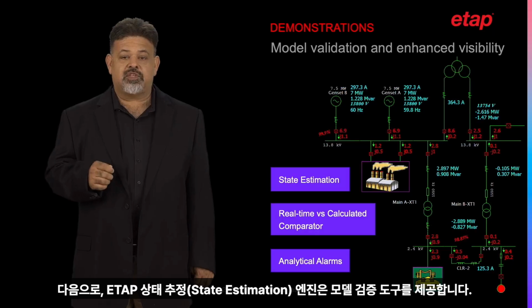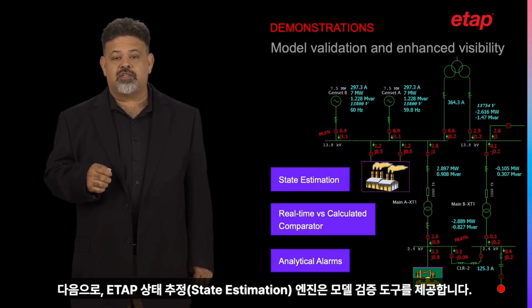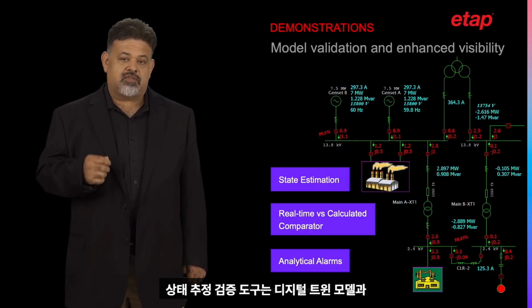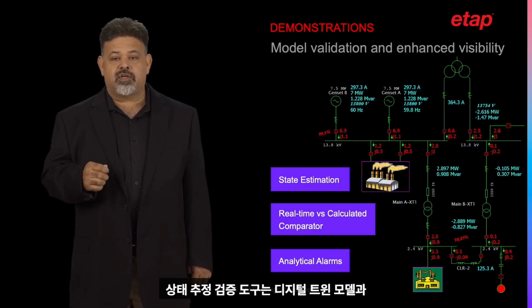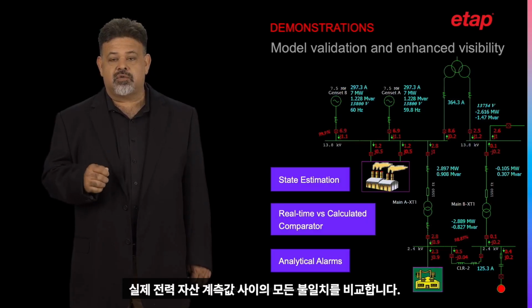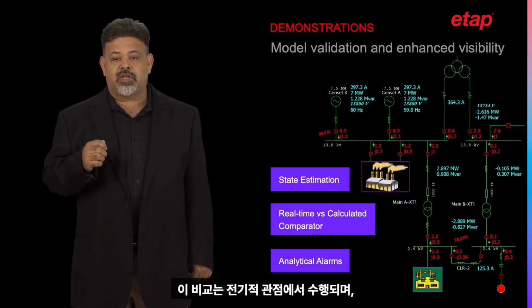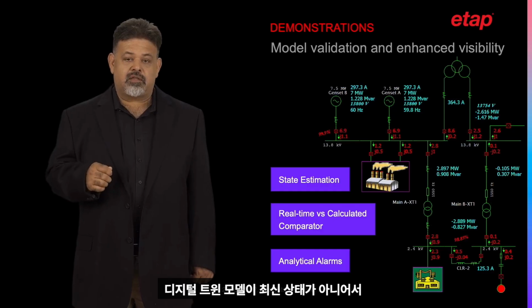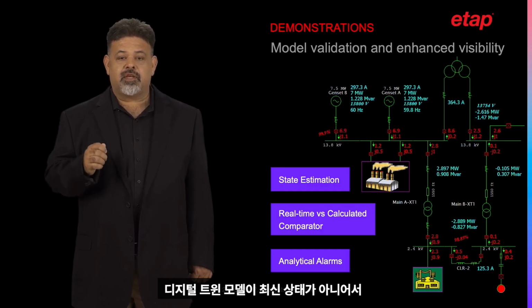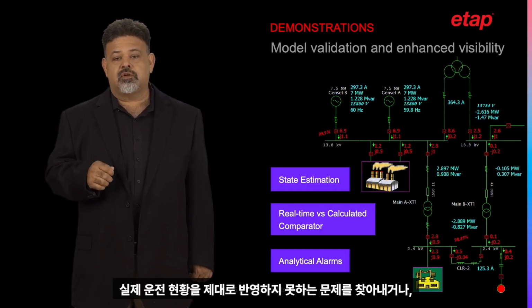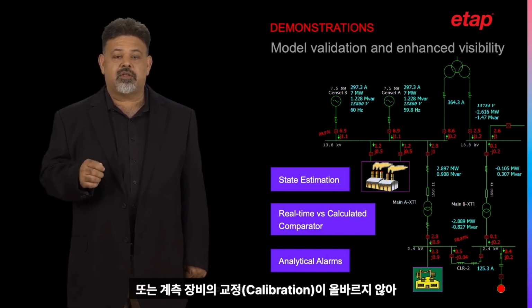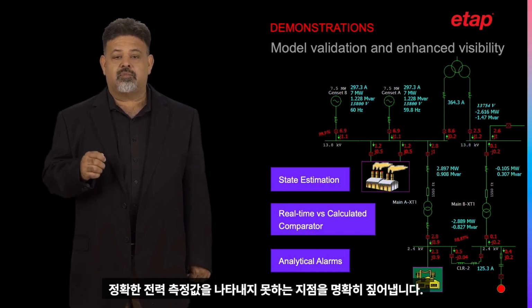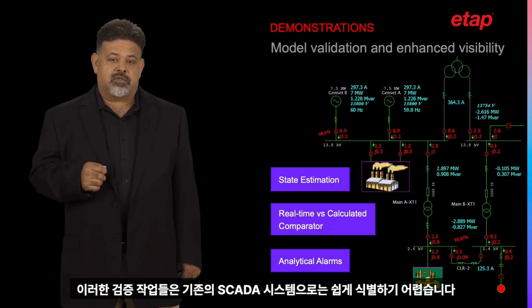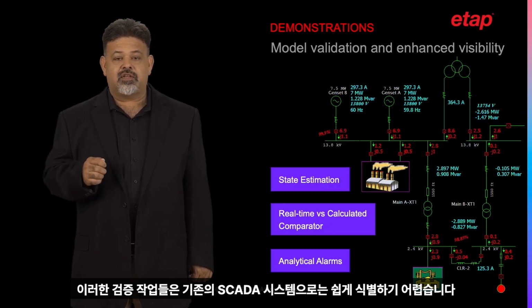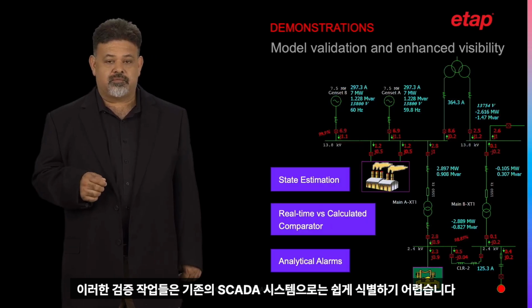Next, the ETAP State Estimation Engine provides tools for model validation and enhanced visibility. The State Estimation Validation tool compares all the discrepancies between the existing digital twin model and the electrical asset measurement. This comparison is done from an electrical perspective, bringing to light issues that the digital twin model may not be up to date to reflect the actual operation, or where the instrumentation may not be calibrated correctly to represent the correct power readings. Note that any of these validations are not easily identifiable with a traditional SCADA.